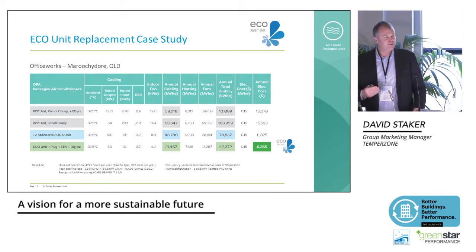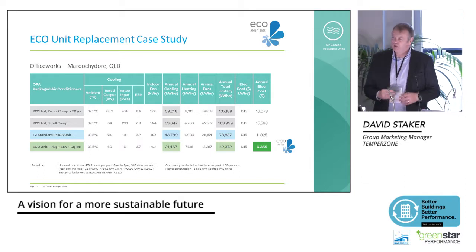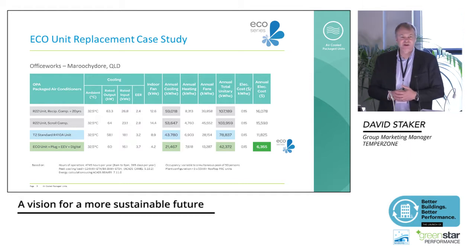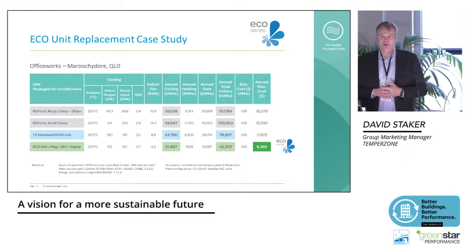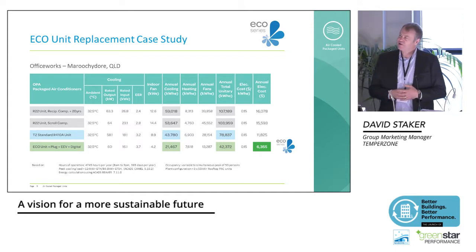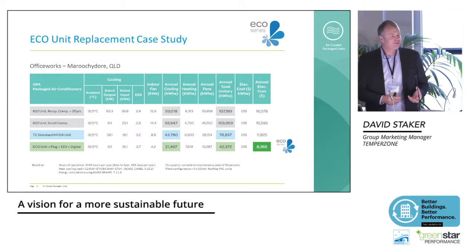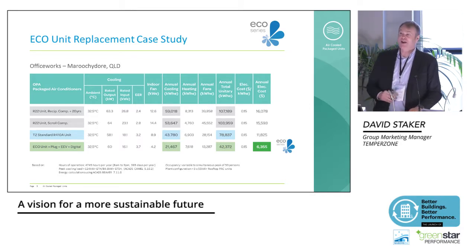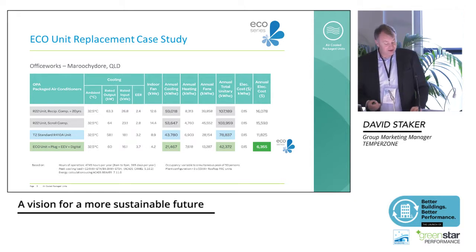As we went through these reviews, we were doing not only theoretical modelling but going out to our customers and asking, can we monitor your equipment? I saw a note up on the screen earlier mentioning Vicinity. We've been doing a case study with Vicinity ourselves, where on one of their shopping centres, we worked out that they were running their plant for 20 hours longer than the stores were open. I reckon that's low-hanging fruit. It's not all about the product. It's often about the life of the building, and somebody's changed the time clock. Instead of changing that one night to late night shopping, we've got late night shopping every night. Some really simple things like that are what we've found.